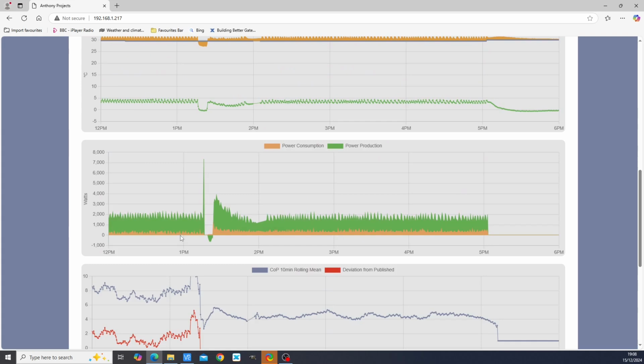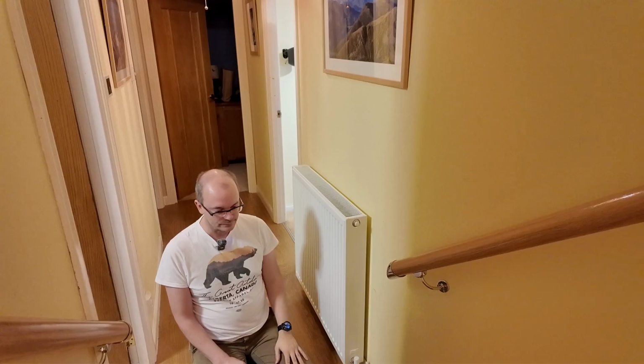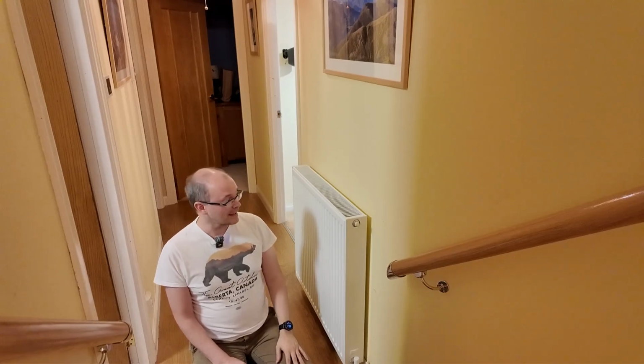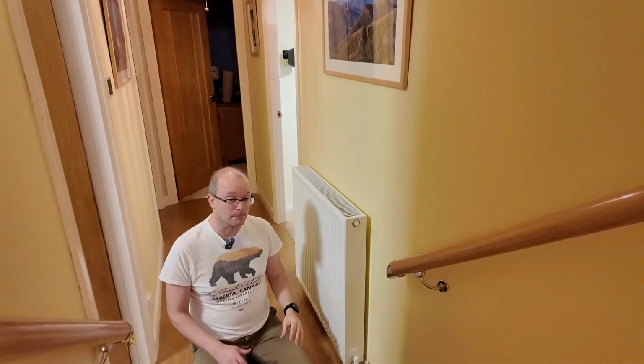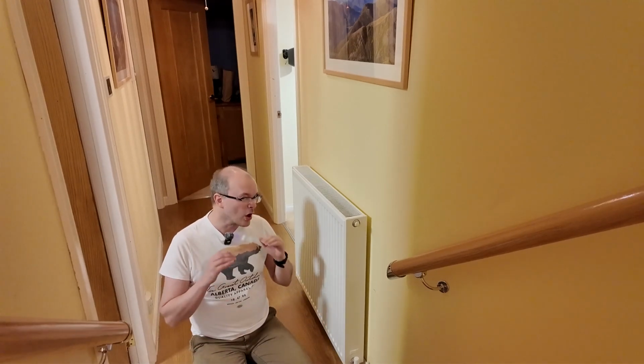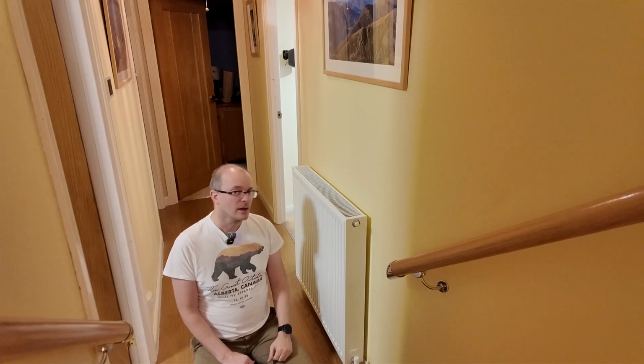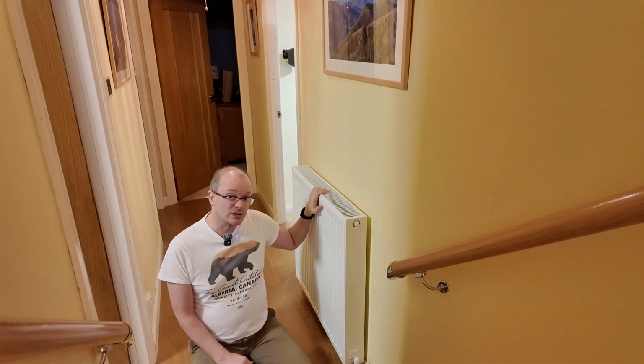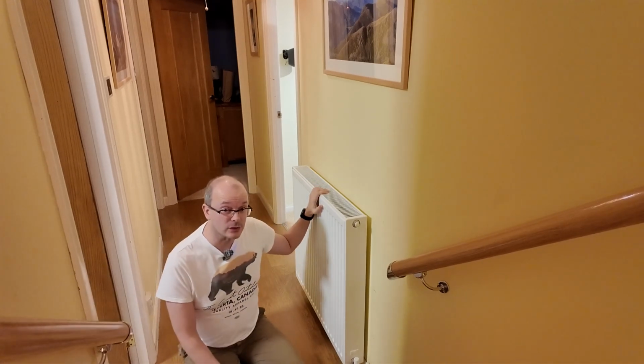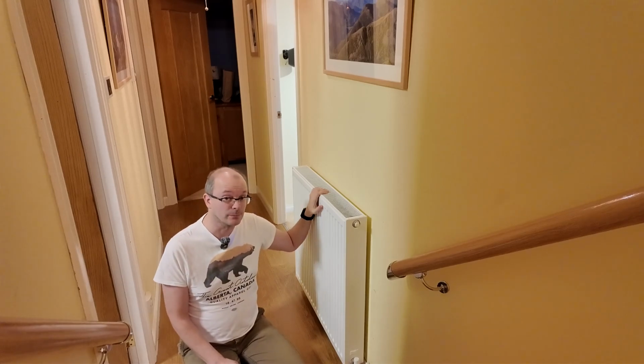And it boils down to the fact that sometimes this heat pump can operate below the minimums by virtue of modulating the compressor to start and stop. And other times it can't. And I don't have any control over this. The fact that I'm able to run my central heating system with a flow temperature no higher than 30 degrees for ambient temperatures higher than 5 degrees Celsius, that's a stunning result.